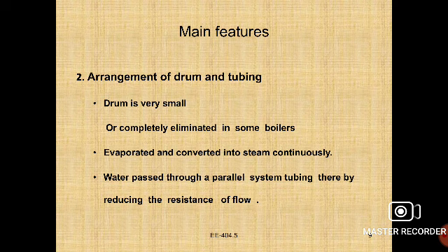The size of the water drum is very small, and in certain cases it is completely eliminated. Water flowing through the pipe circuit is evaporated and converted into steam continuously. To minimize the resistance to flow, the water is passed through a parallel system of tubing.